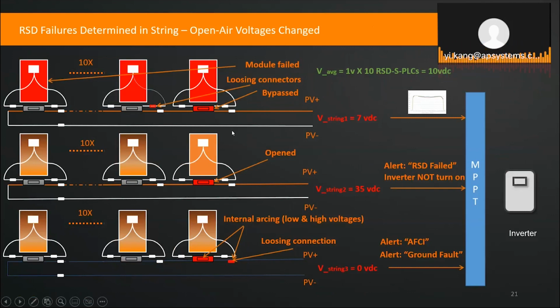That's the reference. So for instance, when we install that, one of the panels fails, like they lost the bypass diode or they have a cracked cell, whatever the reason, the panel failed. Or you have a loose connector. The installer uncertainly didn't connect, or they are using a different type of connector. They're just not fully touching inside. And for any reason, the device has failures or whatever is happening there, normally it bypasses your device. So all those three conditions will bypass these three devices. So you lost 3 volts in that string. So when you measure the open-air voltage for this string, if those three conditions happen, you only get 7 volts DC. Does that make sense to you guys?